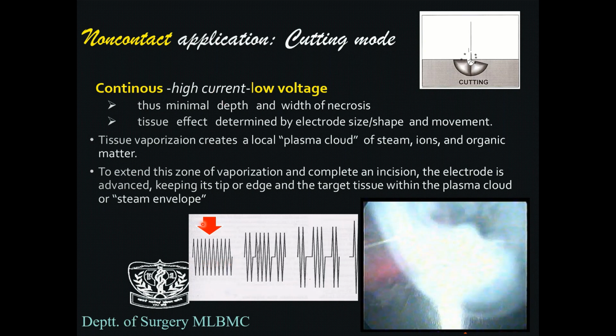Continuous, yes. Low voltage, the voltage is low. So minimal depth and width of necrosis. Why? Because it is not in contact with the tissue. And the tissue effect is determined by the electrode size and movement. Tissue vaporization creates a local plasma cloud of steam, ions and organic matter. And to extend the zone of vaporization and complete an incision, the electrode is advanced, keeping its tip or edge and the target tissue within the plasma cloud or steam envelope.